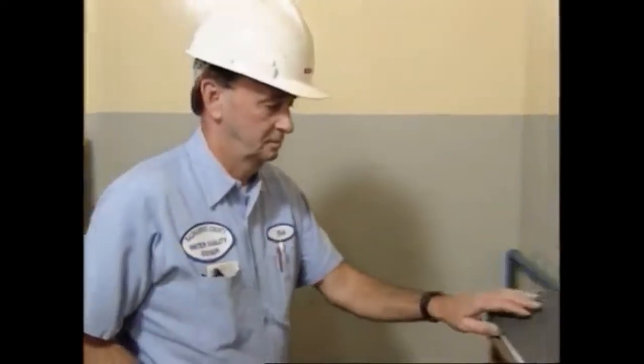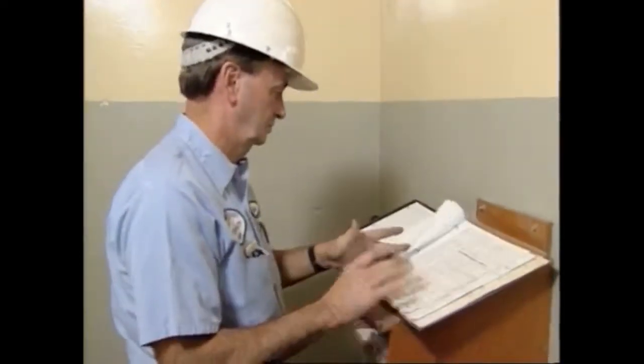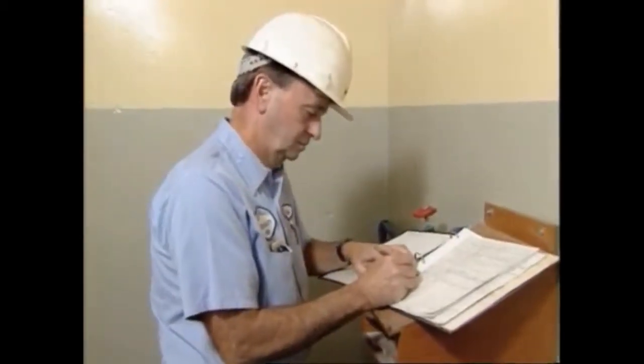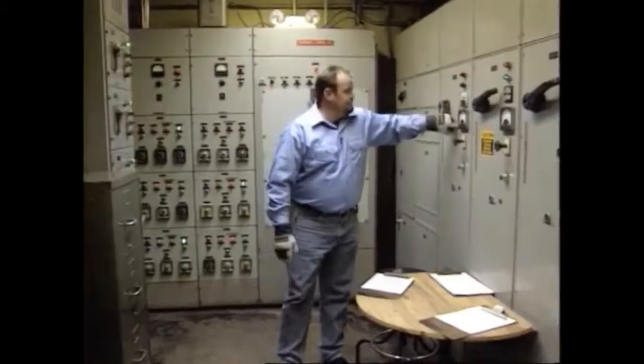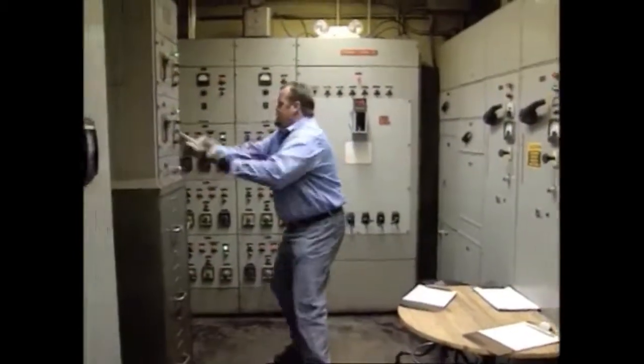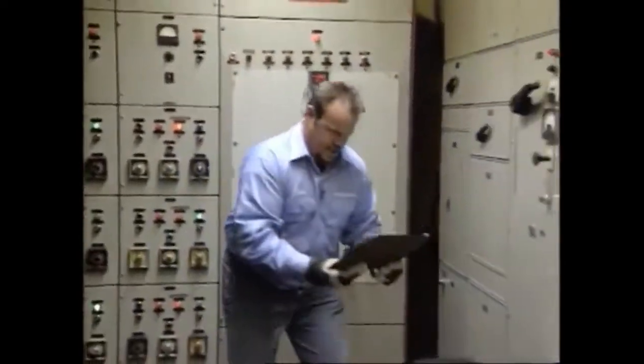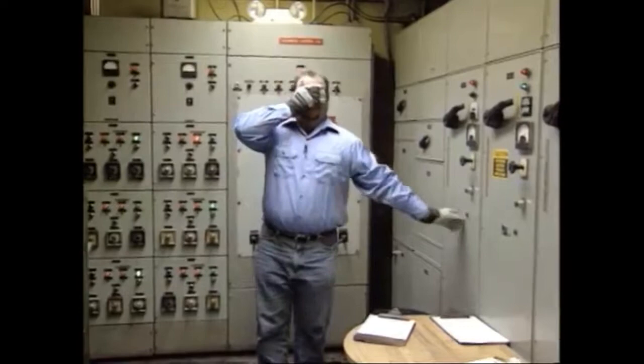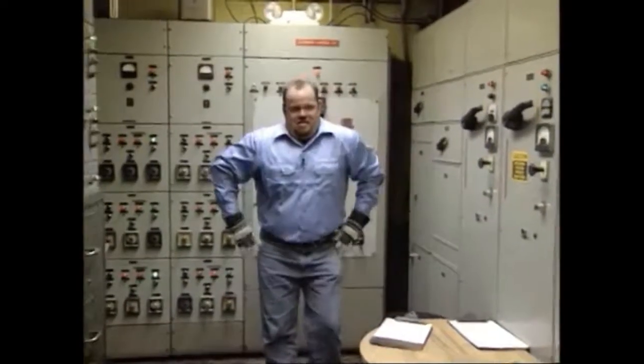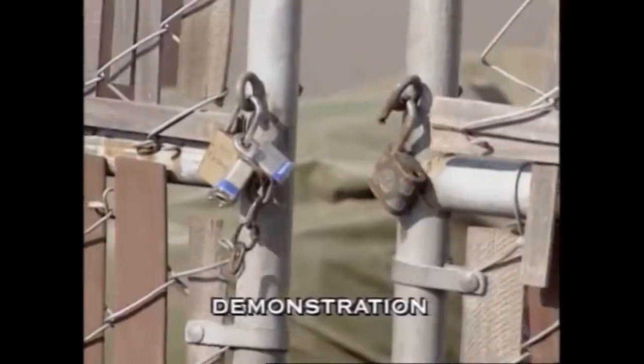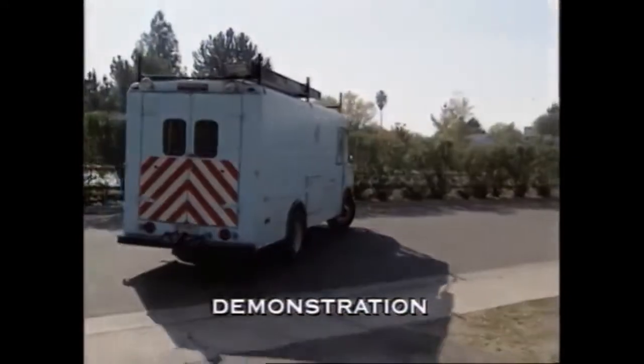Every lift station should have a sign-in log. The larger the operating agency, the more important it is. This practice helps track down changes in station operation, such as pumps turned off, control system changes, and station doors or gates left unlocked. It provides a method for reaching the appropriate person when corrective instructions need to be issued. A sign-in log sheet produces a higher reliability, as a person is going to feel more responsible as their name will be signed in the logbook. No crew wants a station failure a few minutes after their departure because they had neglected something.